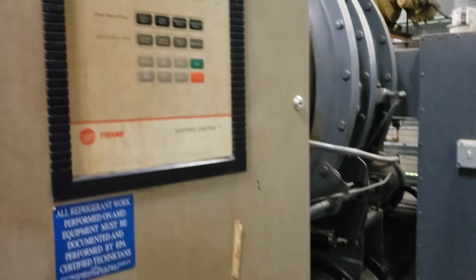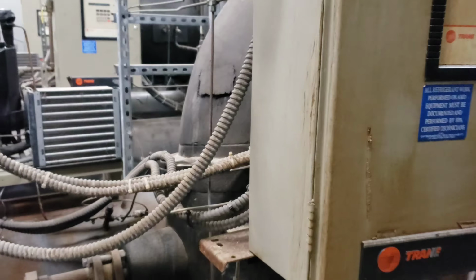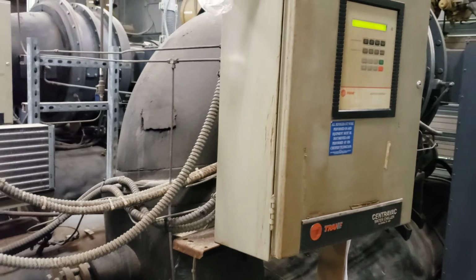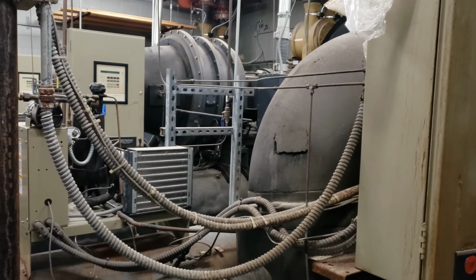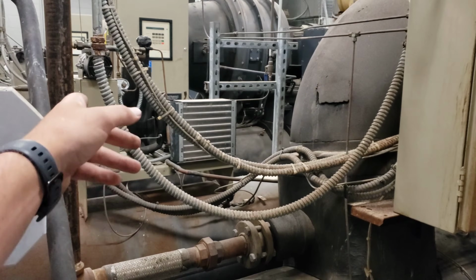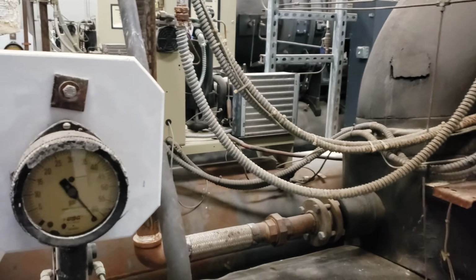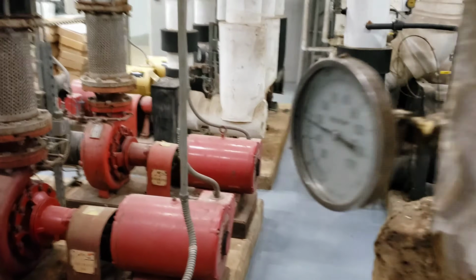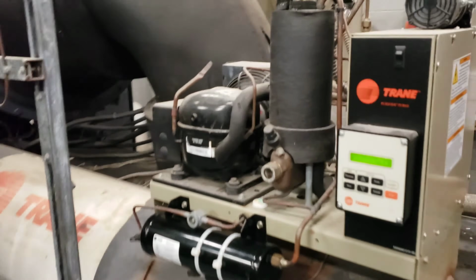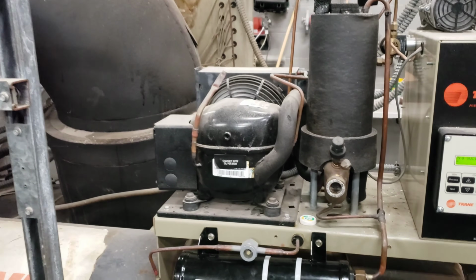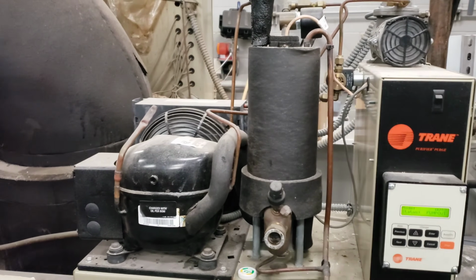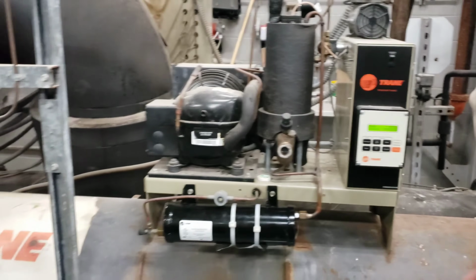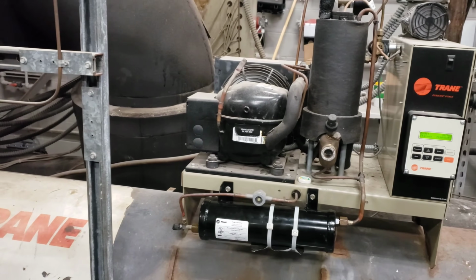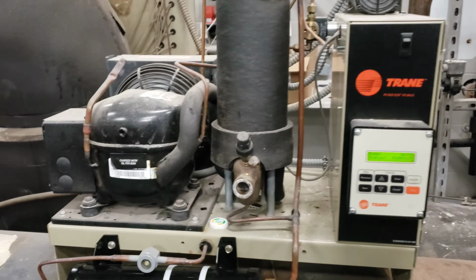It's not had a whole lot of really good maintenance in some time. This chiller, when I got here, was surging, wasn't doing well. Found some issues with the cooling towers, and then I found that the purge unit had some wiring crossed up, and so the purge wasn't actually running with the whole chiller.